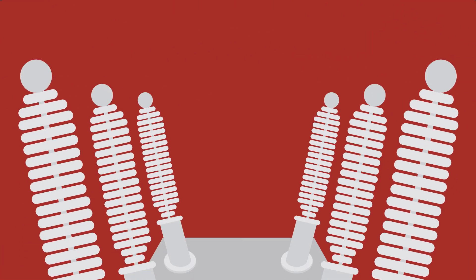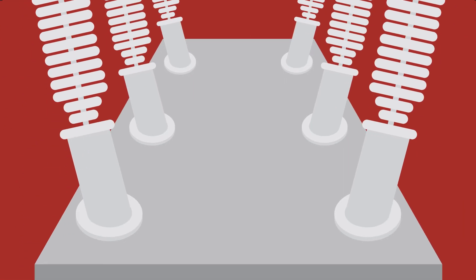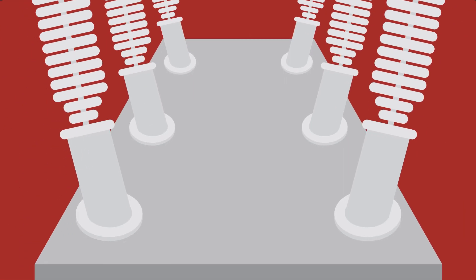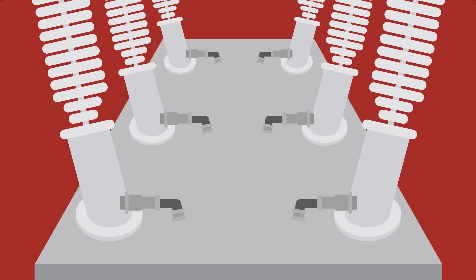The Sum of Currents method requires a current input from each phase of the high and low side bushings to be monitored. This is the most standard configuration and easily retrofitted for legacy transformers.